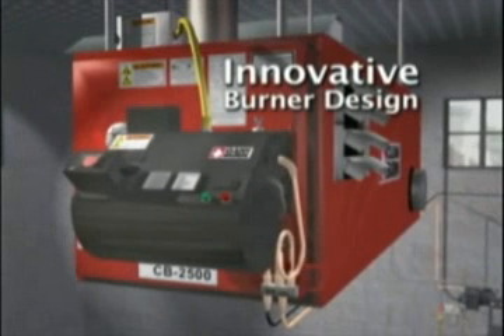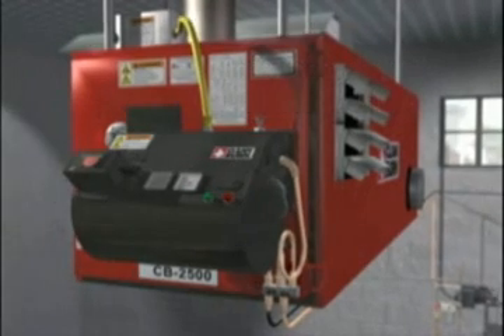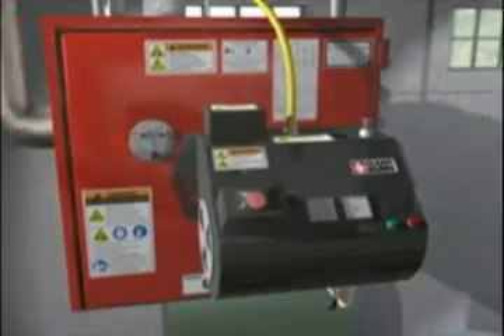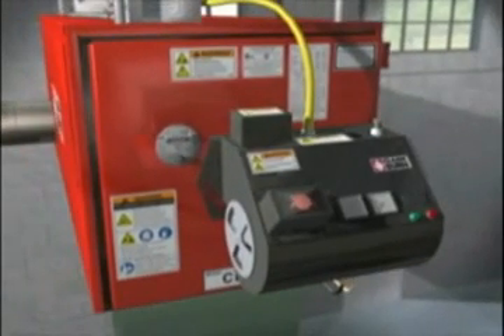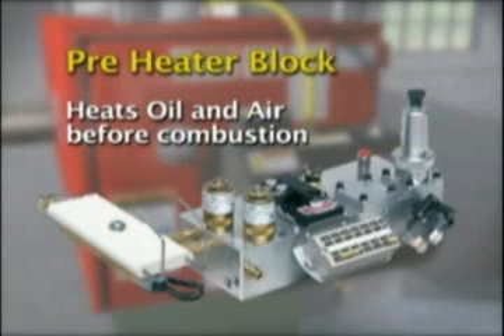CleanBurn's patented oil burner has been engineered from the ground up, specifically to burn used oils. Unlike standard fuel oil, waste oils have a higher flash point and must be preheated in order to ignite properly. CleanBurn's advanced burner design features a preheater block, an ignition system, and a special retention head, resulting in the best burner in the industry. The preheater block heats the oil and air supply to deliver a consistent temperature and oil viscosity to the nozzle, ensuring a complete combustion.